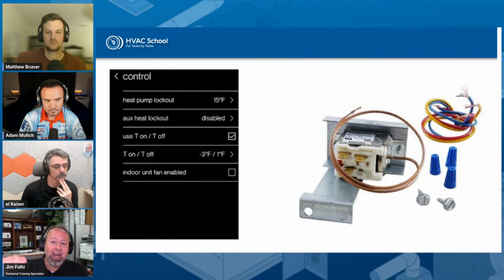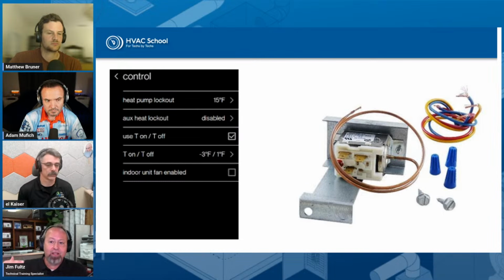And so to be able to cycle that resistance heat, what you really need is an additional wire going outdoors and set up as the second stage of your heat in your thermostat. So you've got your main heat coming through the Y, and then you've got, typically, a W2. That second stage wire is going out to that outdoor thermostat and coming back to the resistance heat, so that when the system has dropped an additional degree and is not able to maintain that house temperature, that resistance heat comes on. Once it goes back up, the resistance shuts back off, but your heat pump is running nonstop through there.